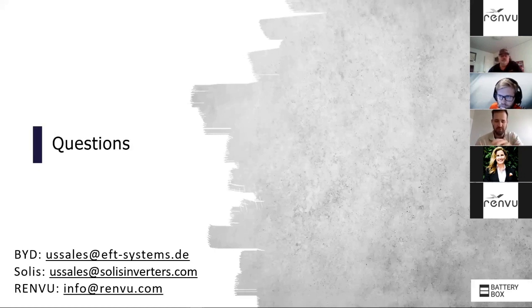The other common question is: when does it stop making sense to add modules? All batteries degrade over time, so you lose a bit of capacity. Based on our highly accelerated life testing, if you used it every day, you'd expect about 80% capacity after 10 years. When you add a module to that stack, it will kind of mirror the degradation, aligning with the old modules. So if you added a module at the 10-year mark, you'd really only be capturing about 80% of that new module's potential. At some point it stops making sense because you're chasing that degradation.